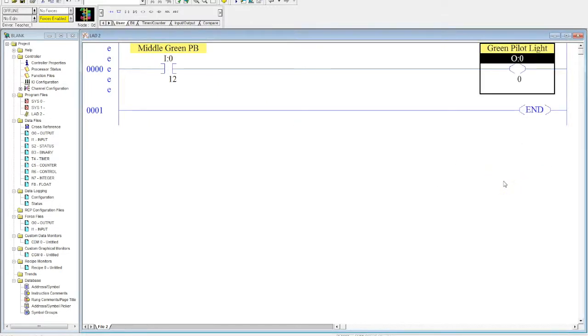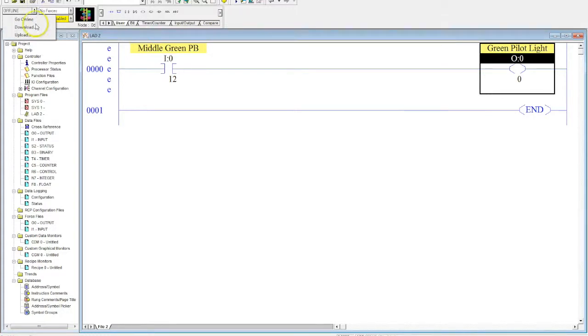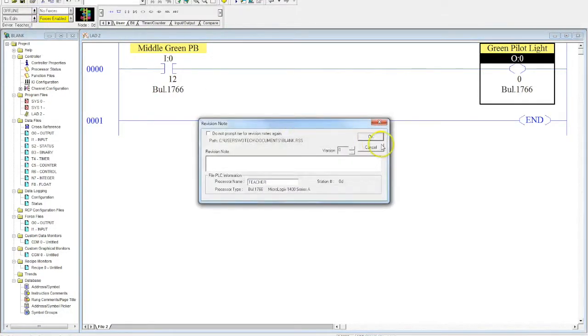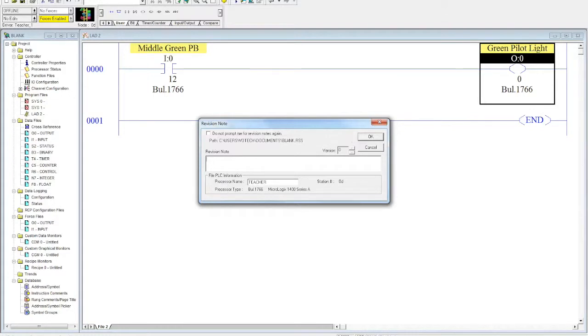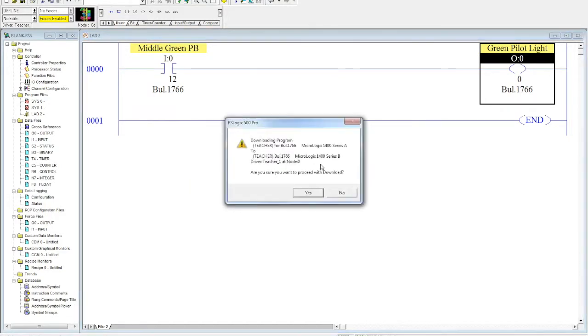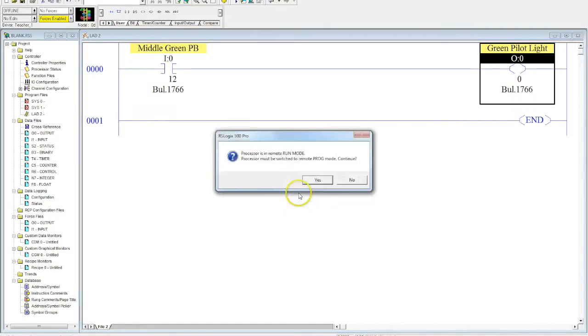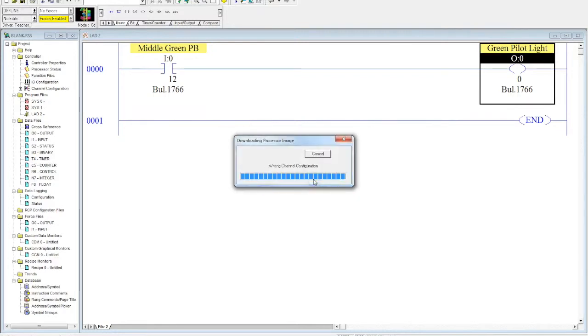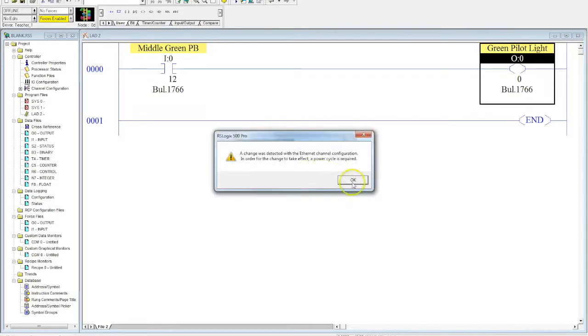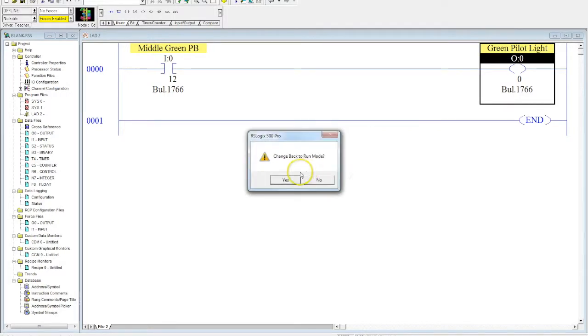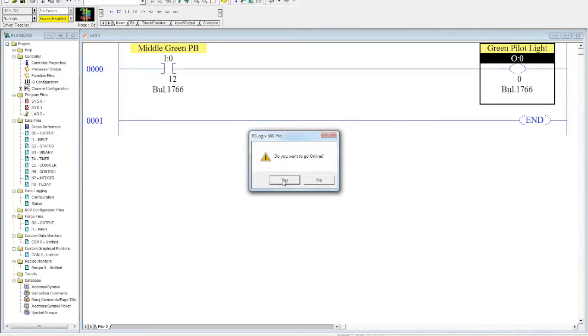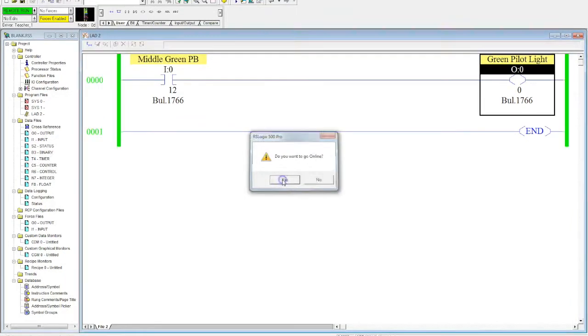Now I have my inputs and my output wired. I'm ready to download. And it's the same steps as when we downloaded the blank program. So we select download. Do I want to put a revision note on here? Let's say added I O. I hit OK. Do you want to change your processors? You select yes. You're in run mode. Do you need to go to program mode? No problem. Select OK here. If there's an Ethernet channel configuration, no problem. We hit yes here. Do we want to go back into run mode? Absolutely. And do we want to go online and watch it? Absolutely. What's the fun in not doing that?